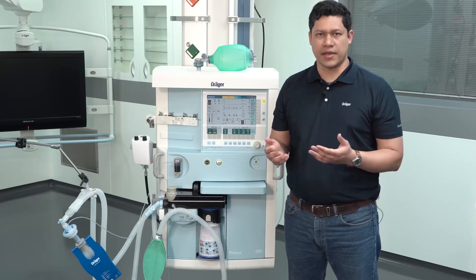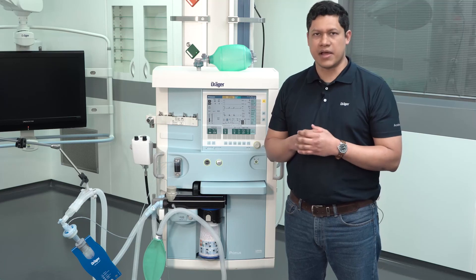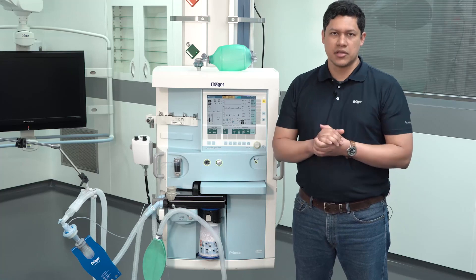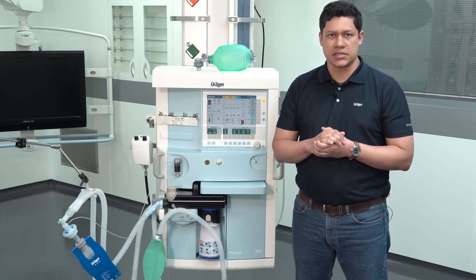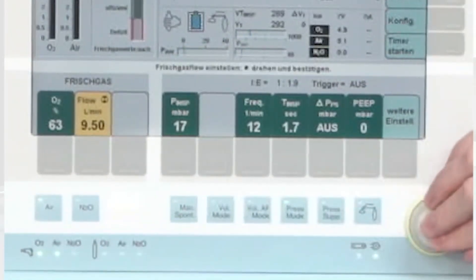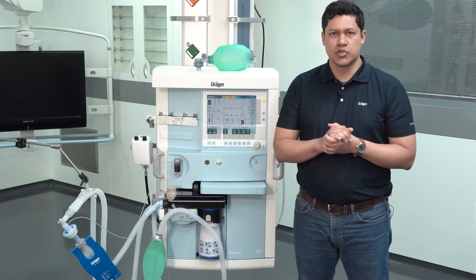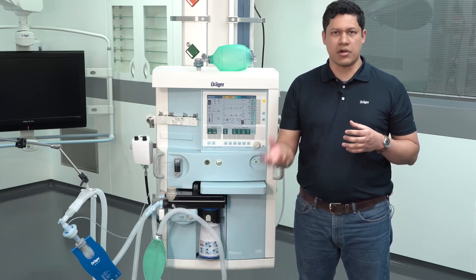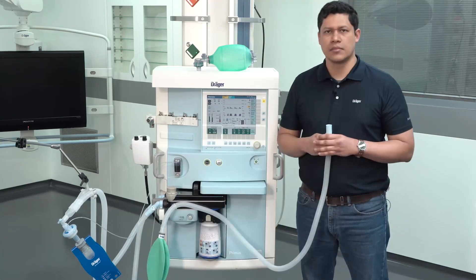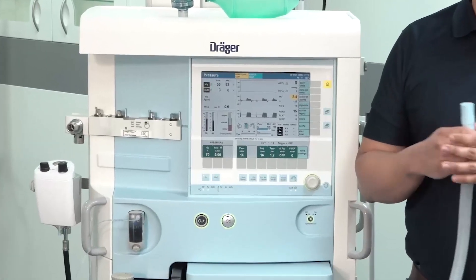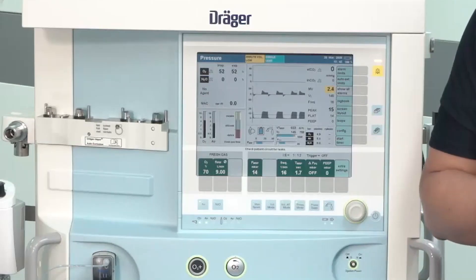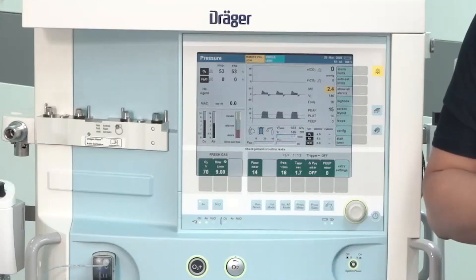In the situation of a deficit of fresh gas flow — identified by an empty manual breathing bag — you have to act immediately. You should identify and correct the leakages and increase the fresh gas flow. Additionally, you can detach the manual breathing bag to allow ambient air to be drawn inside the anesthesia device. Keep in mind that FiO2 measurement will be between the set percentage of oxygen in the fresh gas flow and 21% oxygen in ambient air.